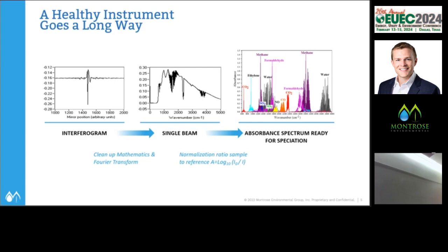It's not a perfect instrument, right? There's certain things that work better than others. But FTIR is really darn good for most combustion-based compounds, especially in the turbine world, gas world. It works really, really nicely, and it's real time. So rather than you taking samples and sending them to a lab, you get results on site. So you kind of know if you pass or fail.